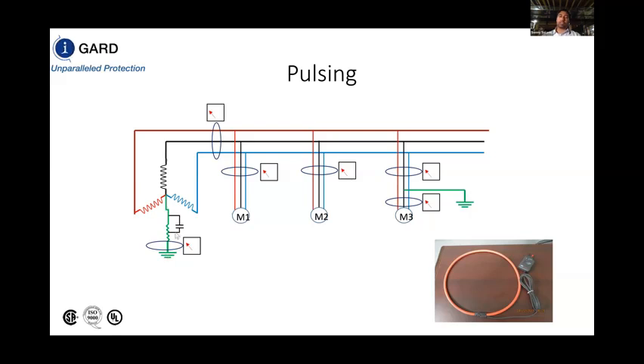The pulsing feature basically opens and closes this contactor that is shorting out half the resistance. As a result of shorting and opening this contactor, we're adjusting the current signature flowing back to the point of fault. So it's flowing between 5 amps and 10 amps, or 2.5 and 5 amps. It's going to take the path of the fault, and you may use a Rogowski coil hooked up to your Fluke multimeter to locate the position of this fault, track it, and provide corrective action.